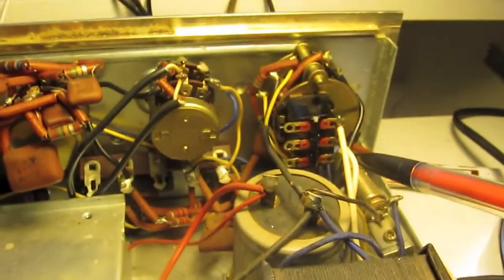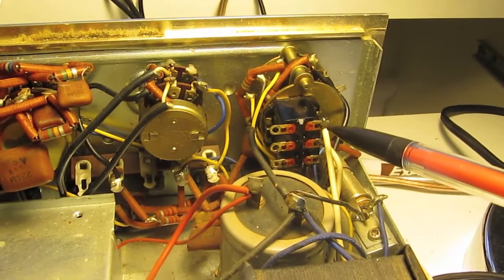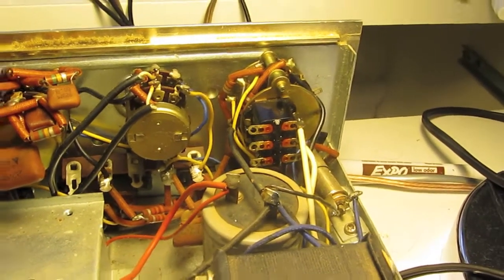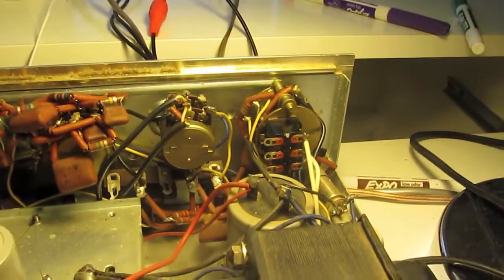Additionally, camera went funny with colors. Additionally, the main switch up here has the connections to allow both the active and neutral to be isolated, but those were not used. It only isolates one side of the incoming mains. Going from that mess and the switch and the cord, especially since this thing does have a designated ground point in there on the chassis, that is simply not used.